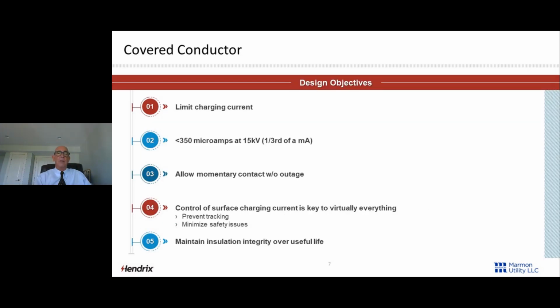The design objective for that covered conductor is that we want to limit the charging current, or limit the surface current that's available on the outside of that jacket. So at 15 kV, we said, well, how about we limit it to 1/3 of a milliamp? So if you touch that conductor with your bare hand and you're wearing a copper suit, you're standing in a puddle, it's raining, you have 0 impedance, you're going to get about 1/3 of a milliamp.